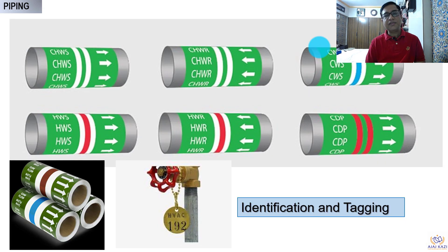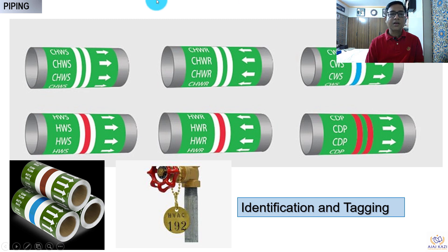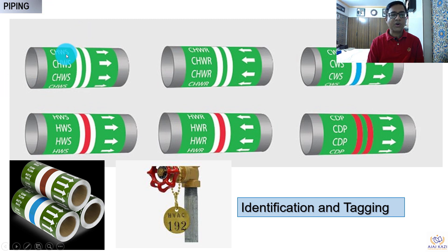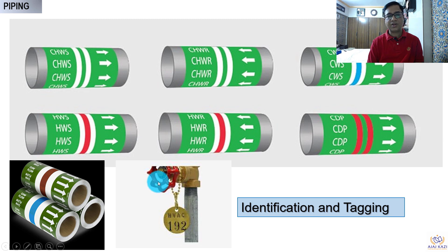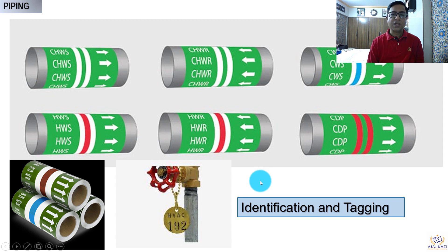Another important thing is identification tagging. When we look at chilled water pipes and condenser water pipes, there are codes specifying what kind of identification to use — color bands and arrows for chilled water supply, hot water systems, and so on. These are available in standards or unit specifications. Similarly, valves are tagged accordingly — for example, HVAC 192 — and there will be a table telling you what that tag number refers to. This is properly correlated with the schematics and your identification system.